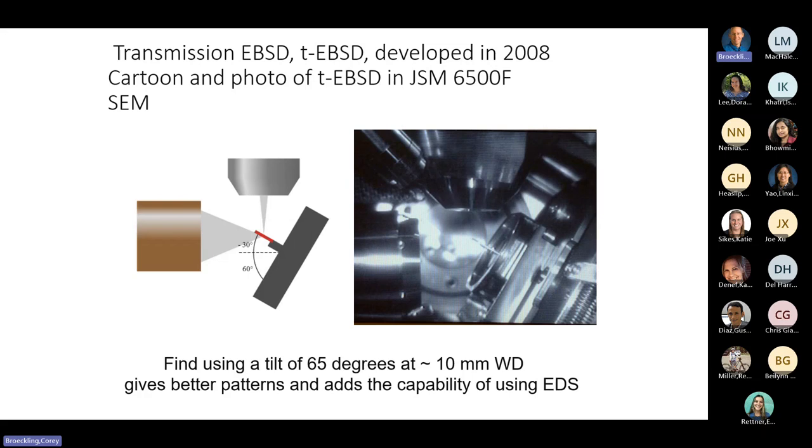Here's transmission EBSD. This was sort of an offshoot of some interest in doing some fine structure analysis. The standard EBSD is in reflection, and so your resolution is probably about 30 to 40 nanometers in diameter. When you go to transmission, you can get down less than 10 nanometers in diameter. The only requirement here is you have to have a sample that's transparent to the electrons.